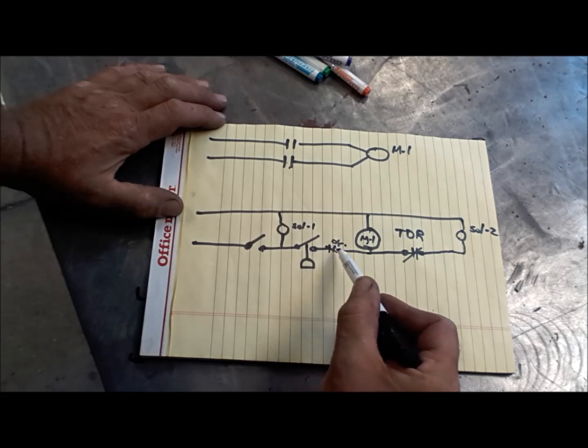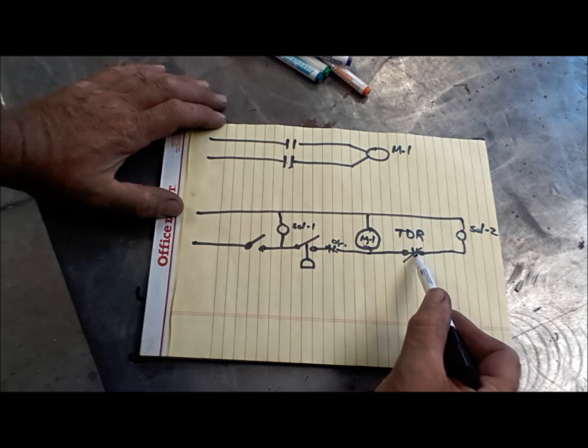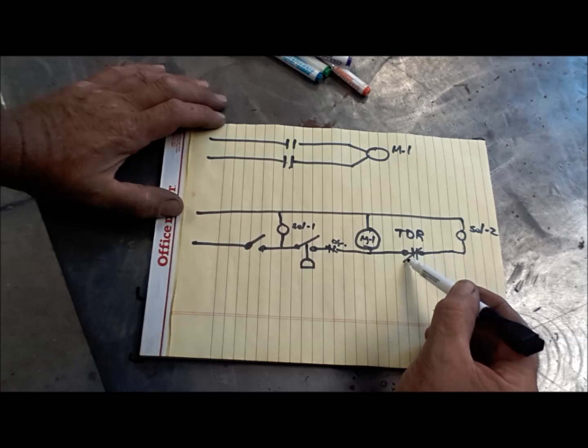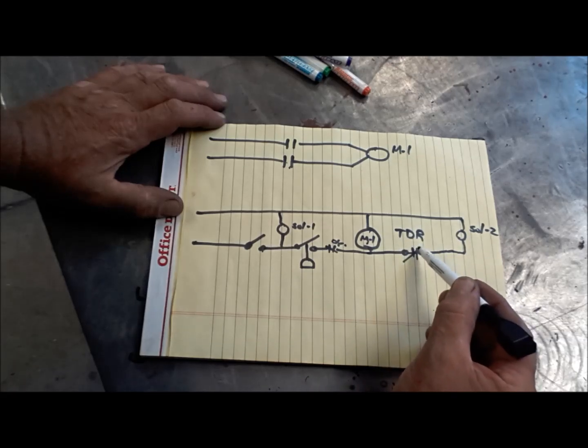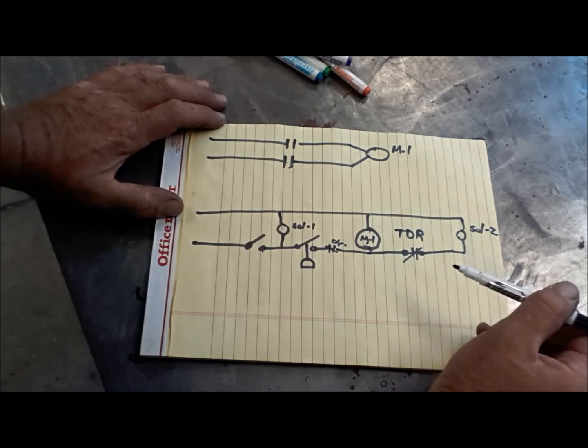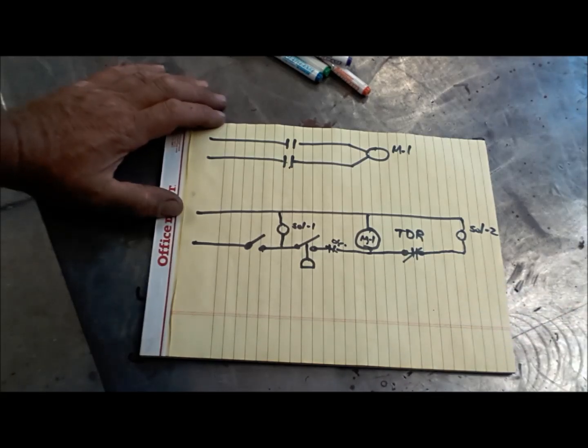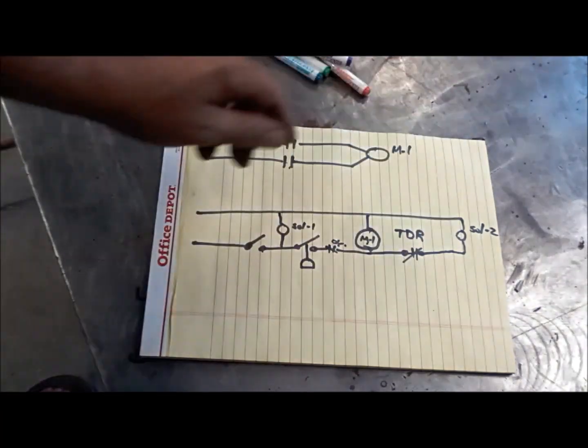But as soon as this M1 coil is energized, TDR is powered up now, time delay relay. It's going to start a timer. This thing's going to stay closed until the timer runs out. And then that switch is going to open. So this drain solenoid is going to only run for one, two seconds. So it's going to give you a quick burst. Every time the compressor cycles, you'll get a very small amount of drainage on the tank. So that's the way it works with a motor starter.